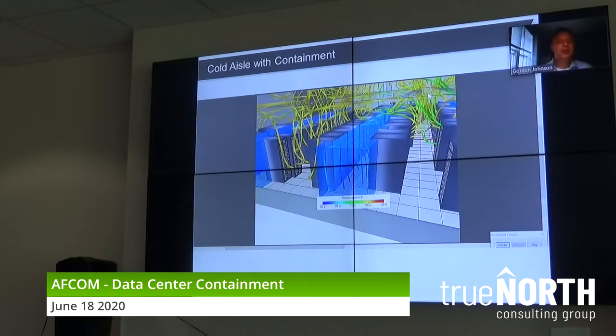I don't want to walk into a hot data center. And while that's true, we want to make your data center hot to walk into, and we're going to do that with cooling optimization. But the act of putting in containment, remember what I said earlier? It doesn't save you money unless you start doing that optimization. In fact, if you put in containment because you have hotspots, like shown in this slide, you solve your hotspots. In fact, if you look at your hot aisles, and you might have to think back about 2 or 3 minutes, before we had much hotter return temperatures in that data center.